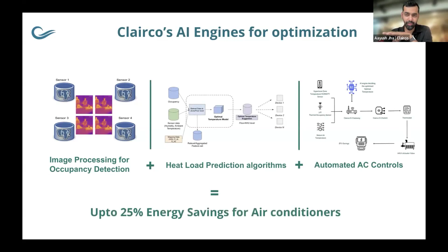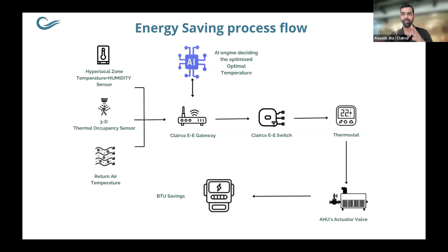What we're doing is looking at multiple sensors interacting with a gateway that sends data to the cloud, or we can do it on-prem as well. This controls your different thermostats in real time — this can be your VAVs, DDC panels, AHU thermostats, or just controlling via the BMS. All four are possible. We can integrate using BACnet, RS485, LoRa, and now PoE as well — we're doing a lot of PoE-based projects as we scale.